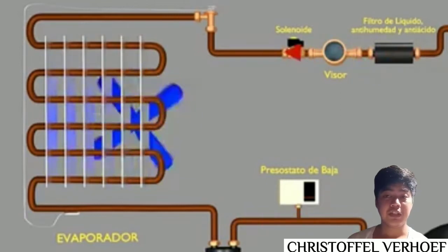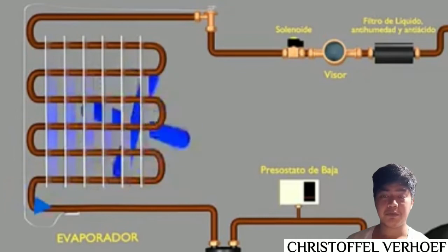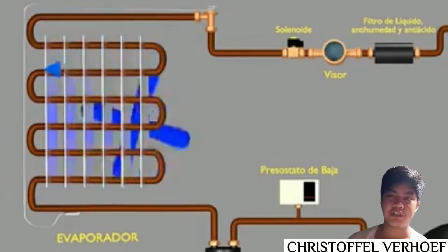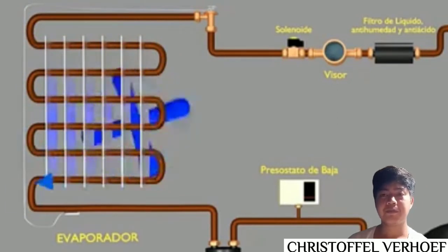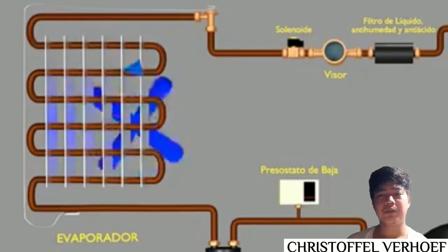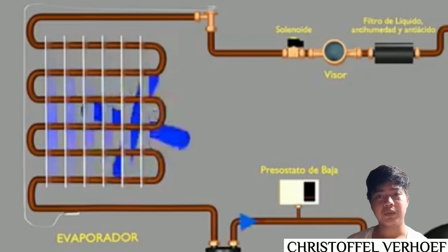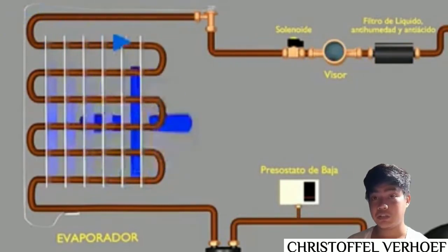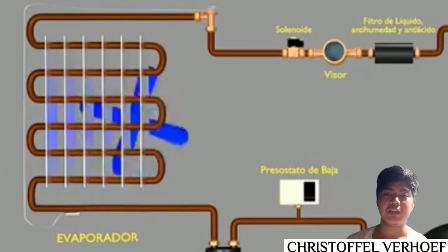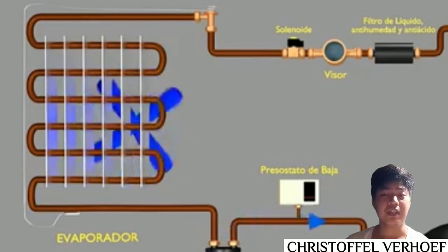The evaporator transfers heat from the refrigerated space into a heat pump through a liquid refrigerant, which boils in the evaporator at a low pressure. In achieving heat transfer, the liquid refrigerant should be colder than the goods being cooled. After the transfer, the refrigerant is drawn by the compressor from the evaporator through a suction line. The refrigerant will be in vapor form upon leaving the evaporator coil.